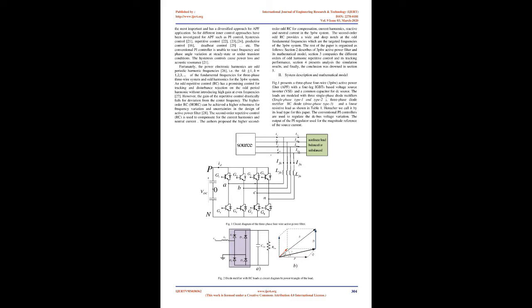The instantaneous reactive power theory method proposed by Akagi [18] and the synchronous reference frame method [19] are the control strategies applied for the 3P4W APFs. In the PQ method, the source is only required to supply the load DC power. All the remaining power of the loads, AC power and zero sequence components power, must be compensated by the active power filter. The IDIQ method works to accomplish this. The source only supplies the mean value of the direct axis component current of the loads.